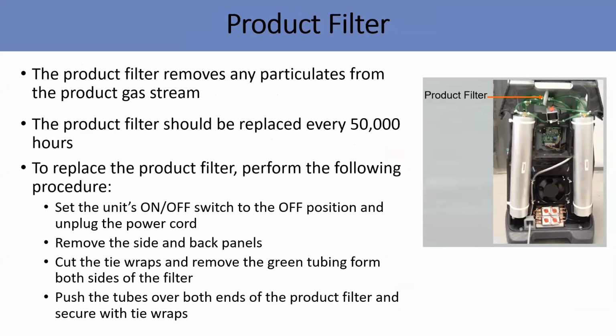Product filter is basically to remove particles from the product gas stream from the output. So you have to replace these every 5,000 hours. Sometimes what happens is, because you don't replace the product filter, it becomes too hard and creates a high pressure system. So you need to replace this product filter every 5,000 hours. But at the same time, if we are using it near an area with a lot of water or moisture, the product filter lifespan can reduce. Be careful with that.